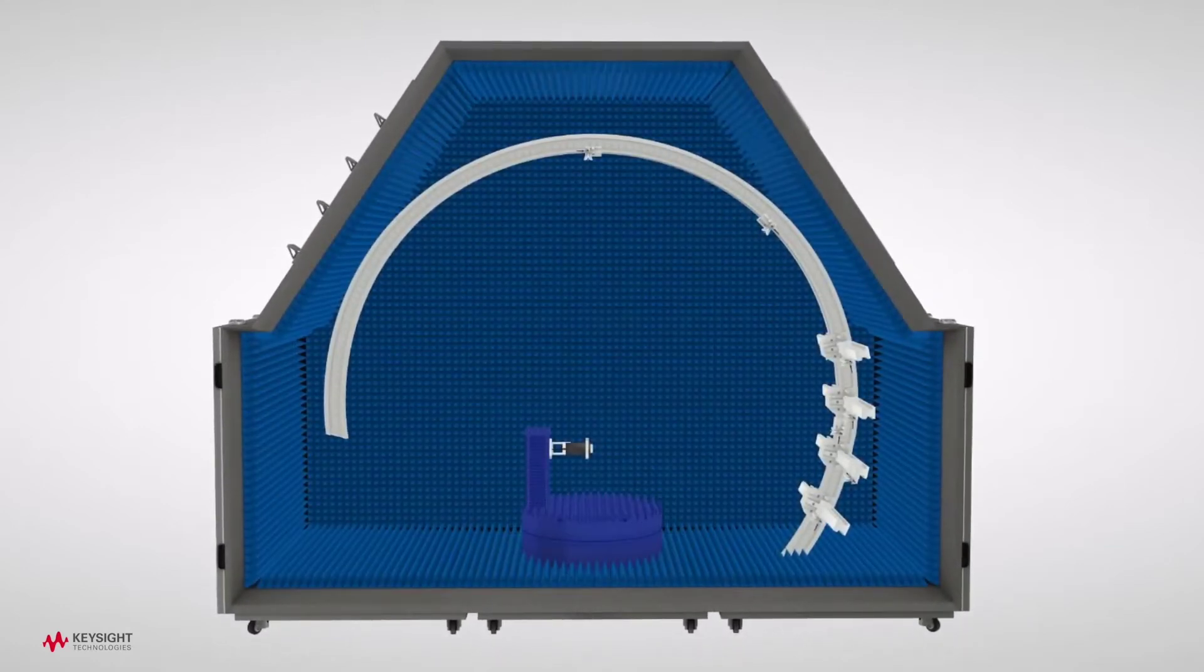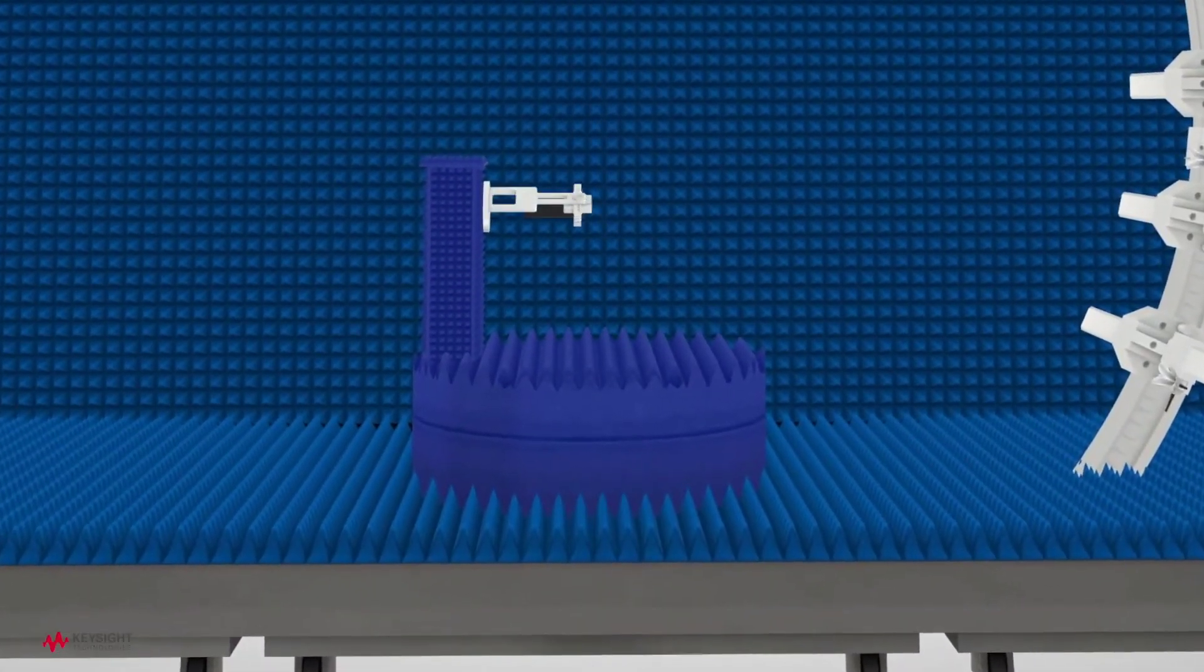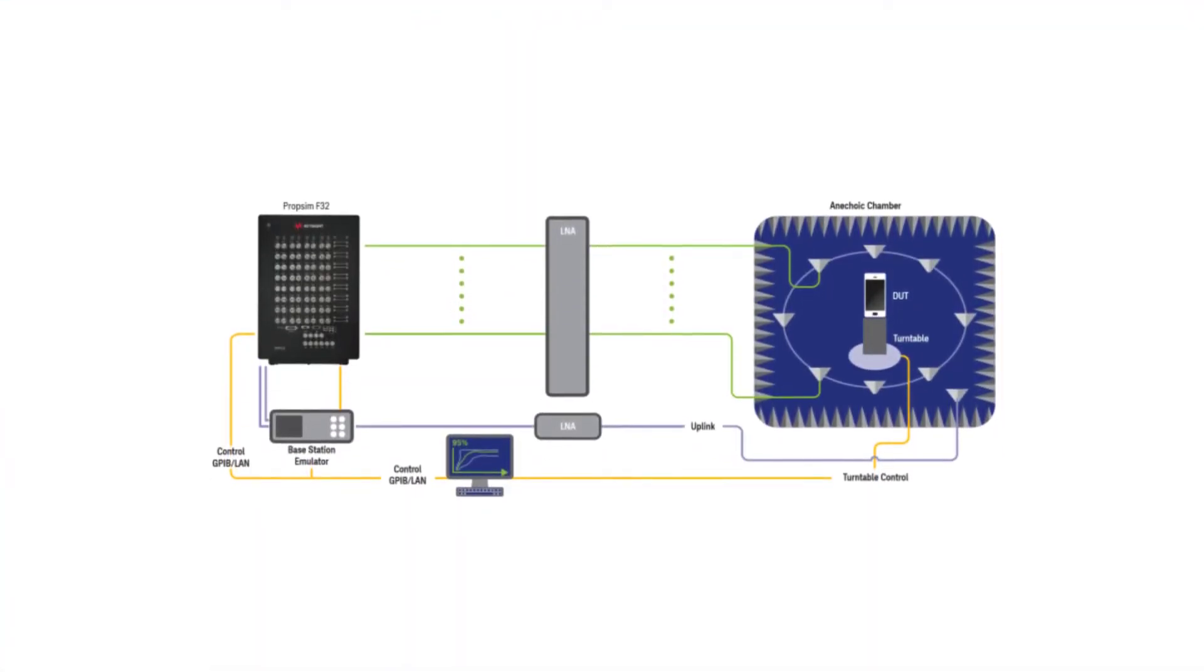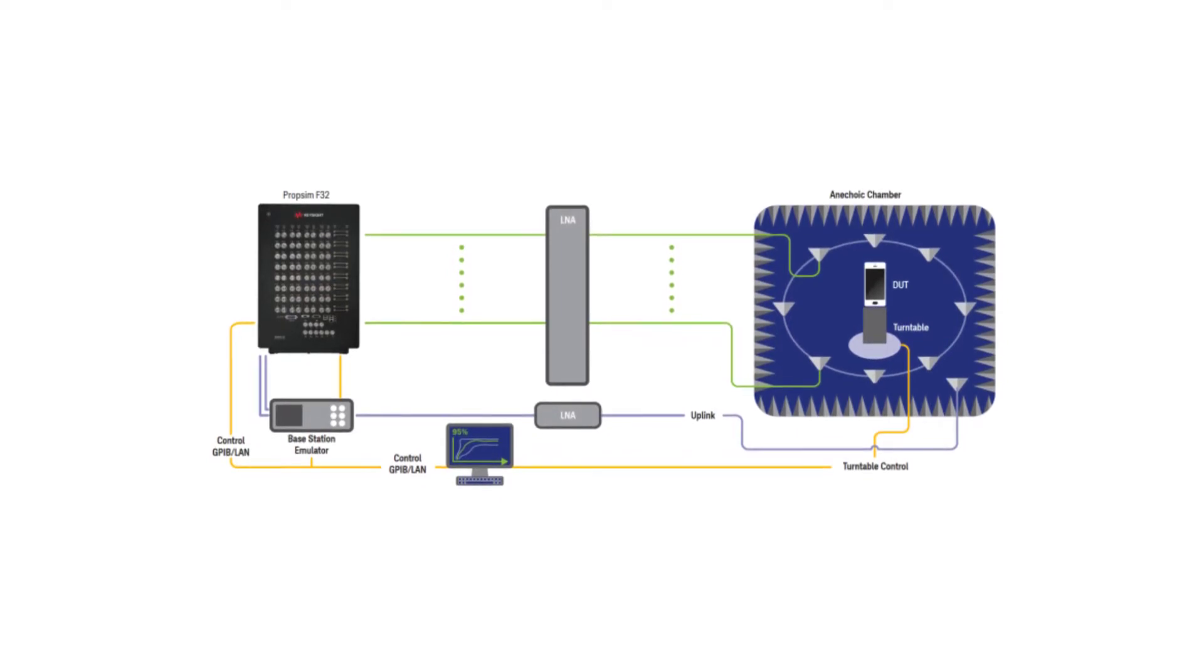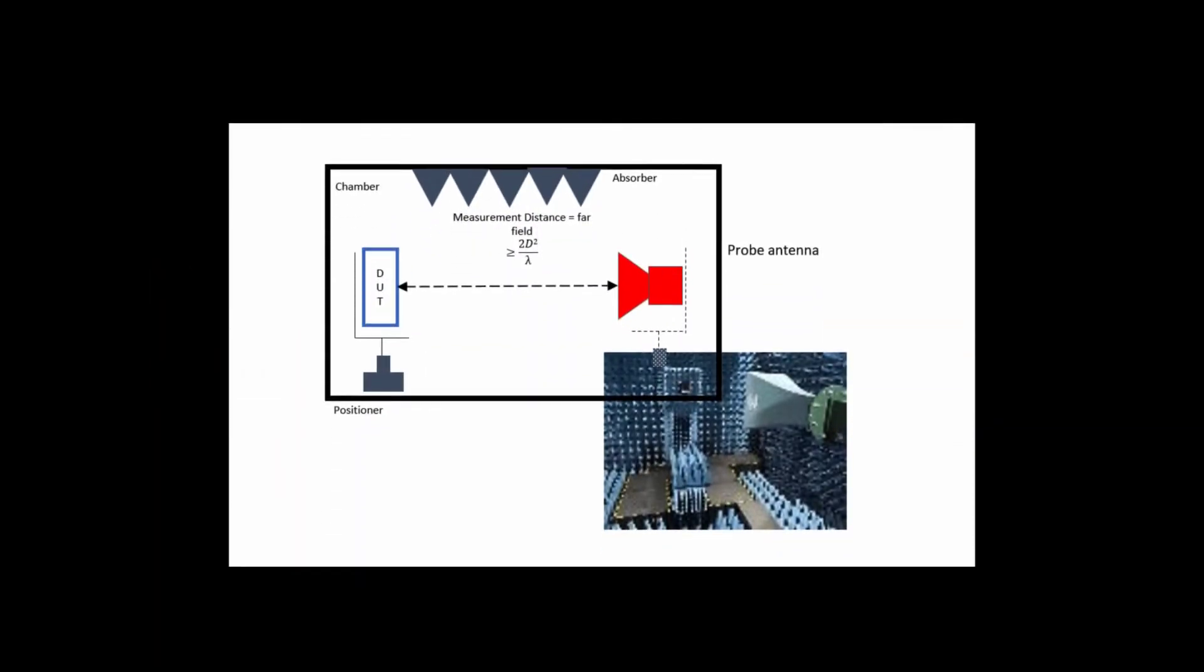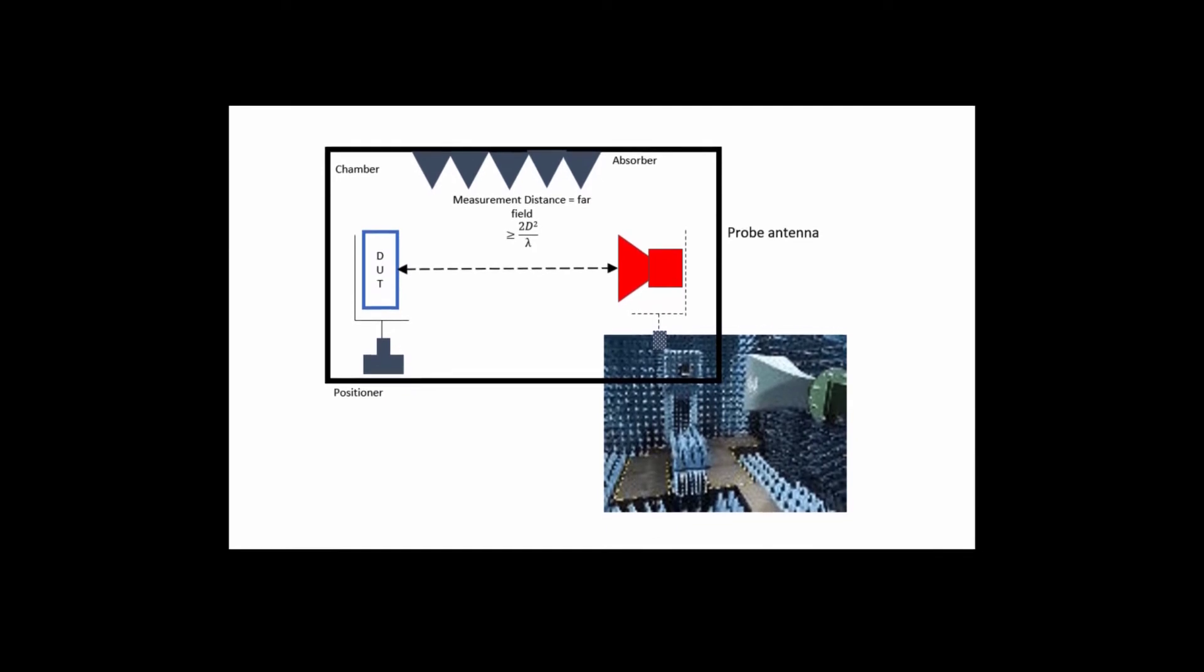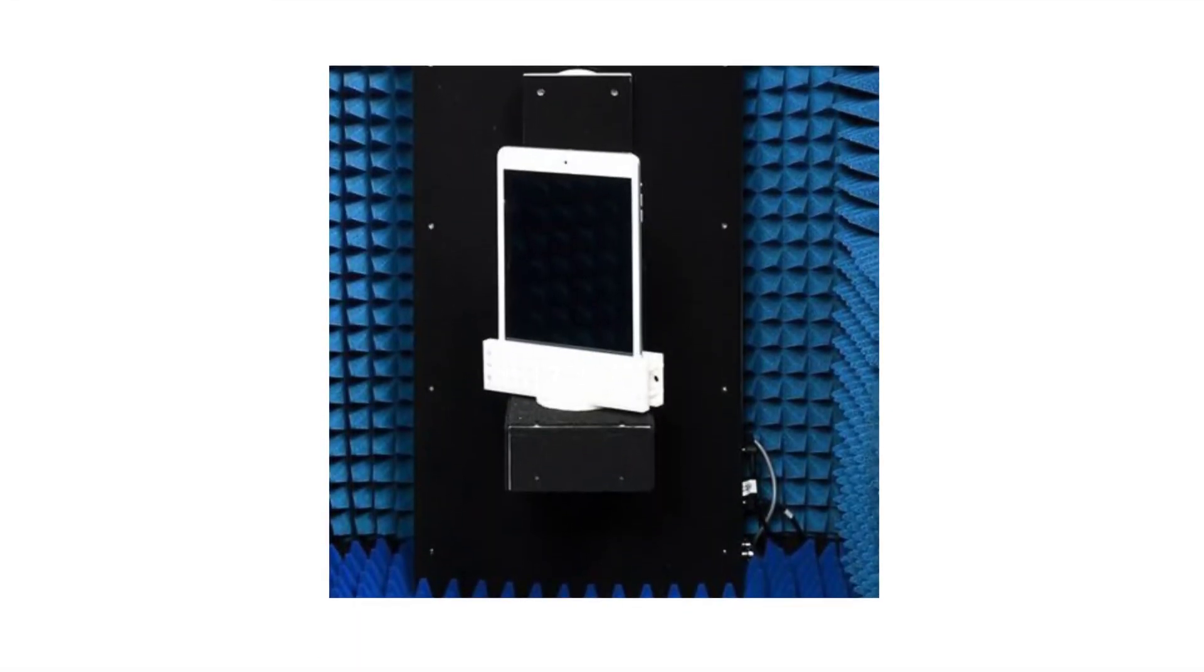Multiprobe anechoic over-the-air test chambers are required for 5G real-world functional and performance testing. The Keysight F9-660A 3D MPAC over-the-air test chamber supports direct far-field tests for phones and tablets up to 13 inches in length.